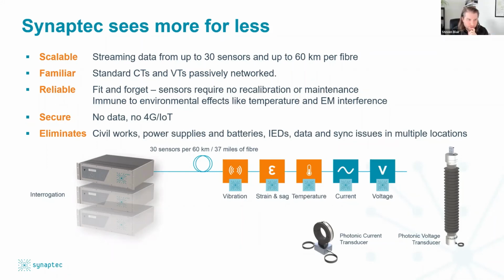Yeah, absolutely. So from a single system, we usually can interrogate about 30 sensors per fiber. So if you need more sensors, you can scale up the number of fibers. And for protection, we typically sample at 4 kilohertz or 4.8 kilohertz. Or if it's more of a measurement or power quality type of application, we can increase that to, say, 14.4 kilohertz, which is just governed by the IEC standard for instrument transformers. So that's presently what we offer.